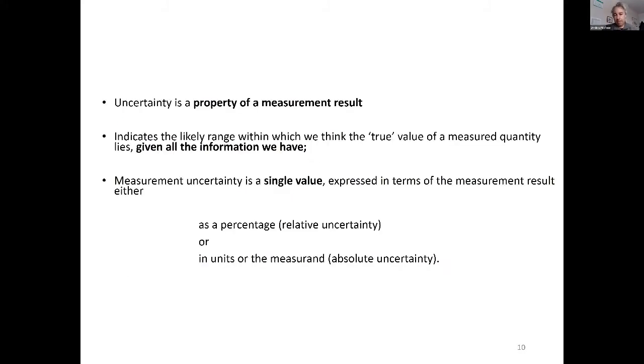So the uncertainty is a property. It tells you the range from to where we think the true value reasonably lies, given all the information we have. It means that with my system, I have to document everything. With my system, my calibrated instrument, including its traceability, etc., reasonably, I can tell you that this sample weighs 2.53 kilograms, plus or minus 10 grams, or whatever it is. It is a single value. You cannot have more than one. And you can express it both as a percent or directly in the units, plus or minus 0.1 gram.